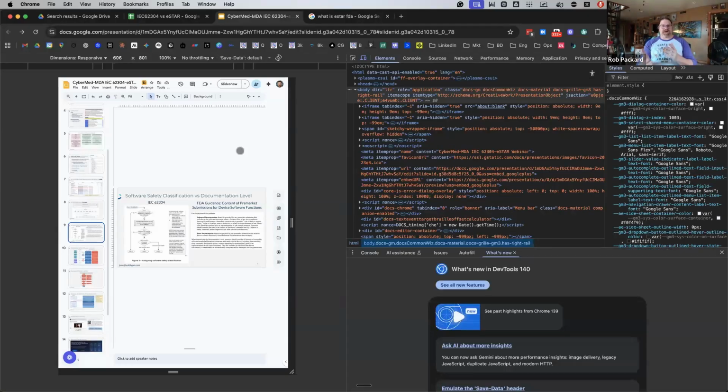Some people don't like that scale, but I find that a lot of things that people want to say are 2s, the FDA says is a 3. And a lot of things people say are not a serious injury, the FDA disagrees. So I tend to go with 3 is a serious injury, 4 is a permanent disability, and 5 is death. And usually people get that pretty well: serious injury, permanent disability, death.